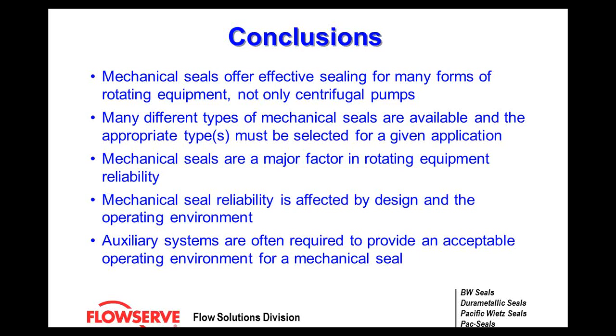Mechanical seals are a major factor in rotating equipment reliability — the mechanical seal is like the weak link in the system. If you have seal failures, there is generally something causing them: operational, mechanical, or design issues. As I was told when I first got into the mechanical seal world, they don't like to commit suicide. If you identify a mechanical seal failure and understand what's causing it, you can backtrack and find other problems in the system that would eventually cause bearing failures or impeller wear.